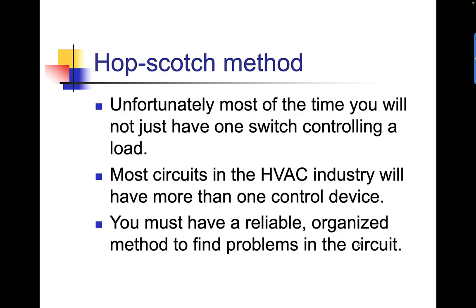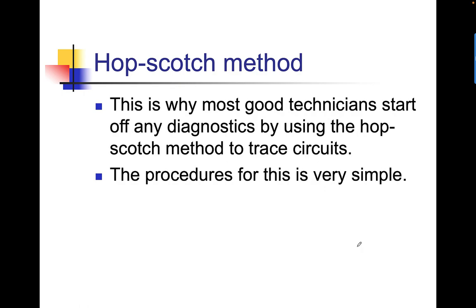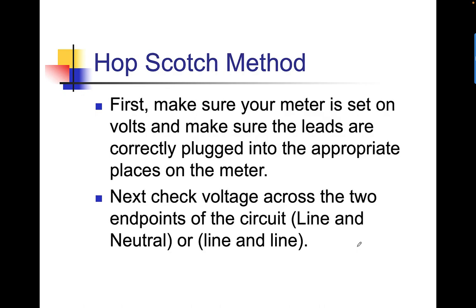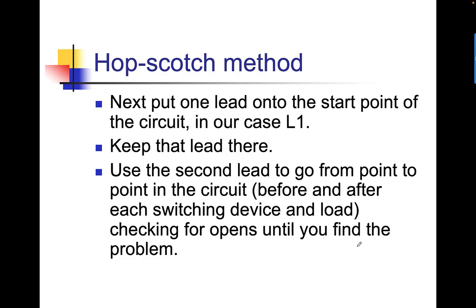Most of the time you'll not just have one switch controlling a load. Most circuits in the HVAC industry have more than one control device. You must have a reliable, organized method to find problems in the circuit. This is why most good technicians start off any diagnostic by using the hopscotch method to trace circuits. The procedure is very simple: make sure your meter is set to volts and the leads are correctly plugged in. Check the voltages across the two endpoints of the circuit — line and neutral, or line and line. Put one meter lead at the start point, in our case L1, and keep it there. Use the second lead to go from point to point in the circuit, before and after each switching device and the load, checking for opens until you find the problem.